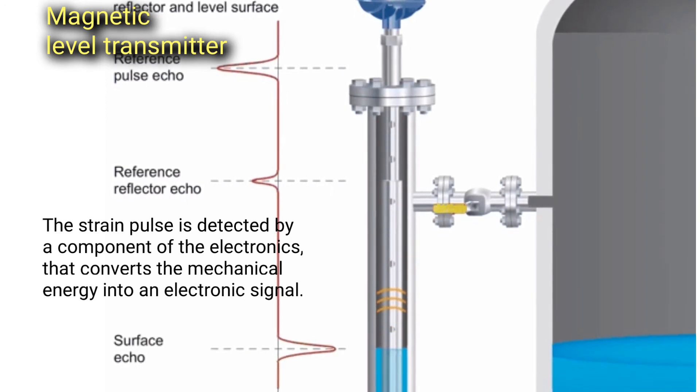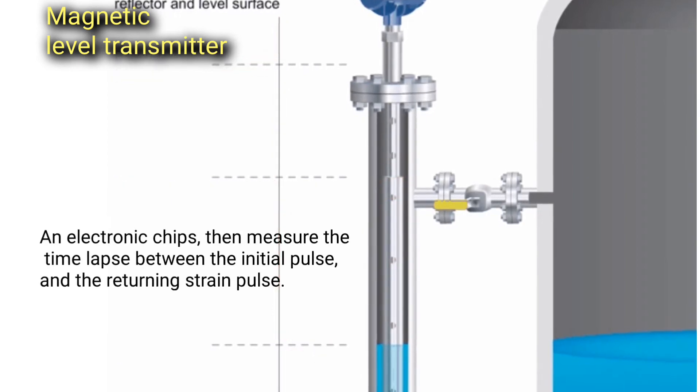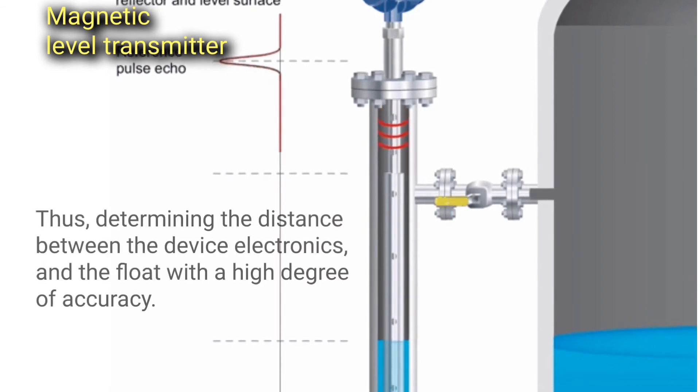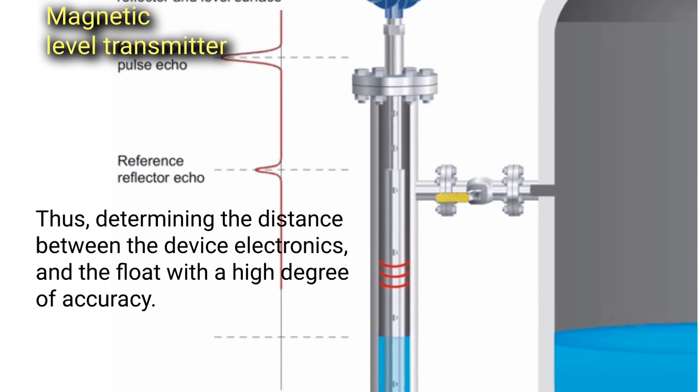This converts the mechanical energy into an electronic signal, and electronic chips then measure the time lapse between the initial pulse and the returning strain pulse, thus determining the distance between the device electronics and the float with a high degree of accuracy.